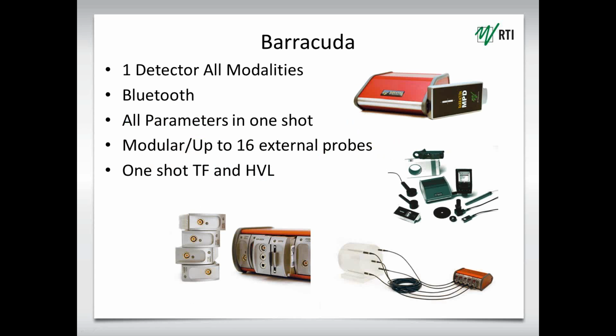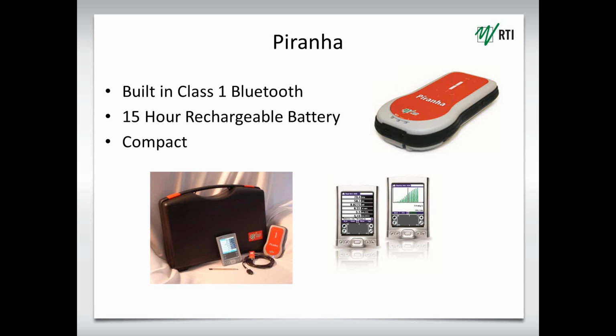We came with our Barracuda. It covered a lot of those capabilities. One detector, all modalities, had Bluetooth, all parameters in one shot. In fact, it was modular. It could handle up to 16 external probes and measure them all simultaneously. We still have many people using them for that application. One shot, TF, total filtration, and HVL. Then we came with our Piranha. We beefed up the internal Bluetooth, 100-meter range, 15-hour rechargeable battery, compact, a wireless display, and we had a successful device.